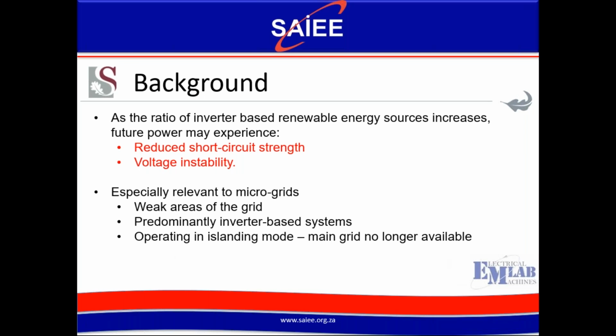As the ratio of inverter interface renewable energy sources increases, future power systems may experience a reduced short circuit strength due to the lack of rotational inertia present in the system. When a power system short circuit strength is insufficient, it becomes more susceptible to voltage instability caused by load changes or faults. This issue is especially relevant to microgrids, which are typically located in weak areas of the grid and predominantly comprise of inverter interface, solar PV, and wind turbine systems. This problem is further exacerbated when the microgrid operates in islanding mode, where the main grid is no longer available to supply a fixed reference voltage for the inverters or to supply the short circuit current required to trip the circuit breakers within the microgrid.